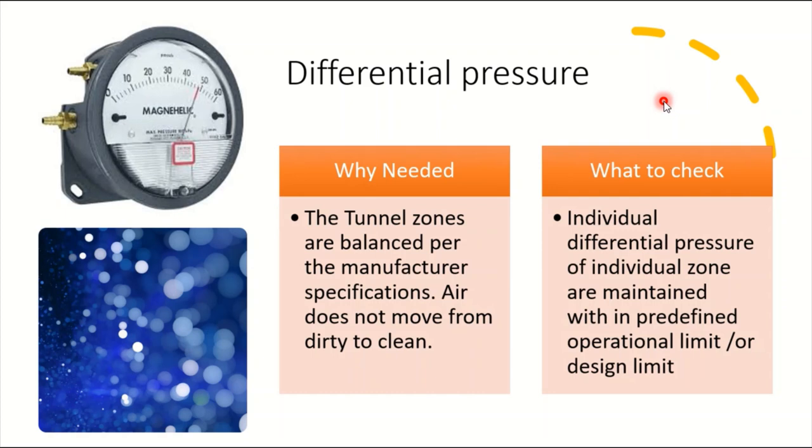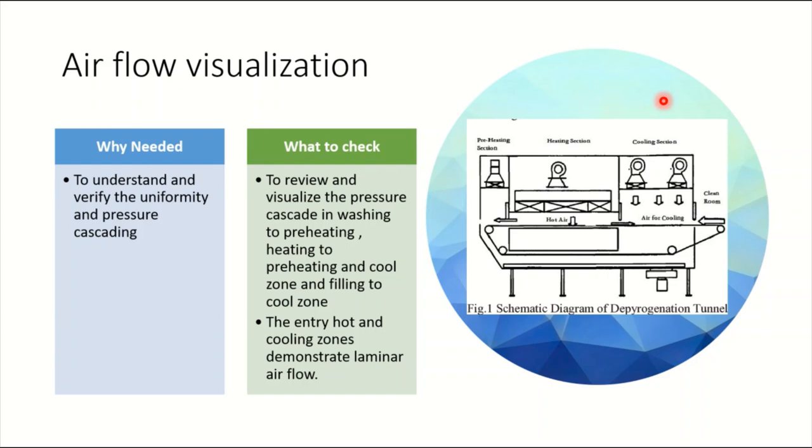Differential pressure is very important, giving identity to every zone. If differential is not maintained, then your temperature distribution will not be uniform. Even when talking about differential pressure within the chamber and the filling room, if filling room pressure is excessively high, it starts pushing the entire pressure towards your washing machine. You can feel your washing station is getting heated. Pressure balance is one of the important aspects. You should look into your design specification document and establish and monitor this reading accordingly.